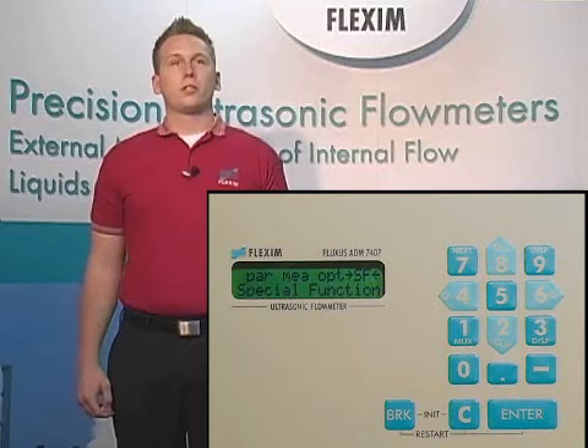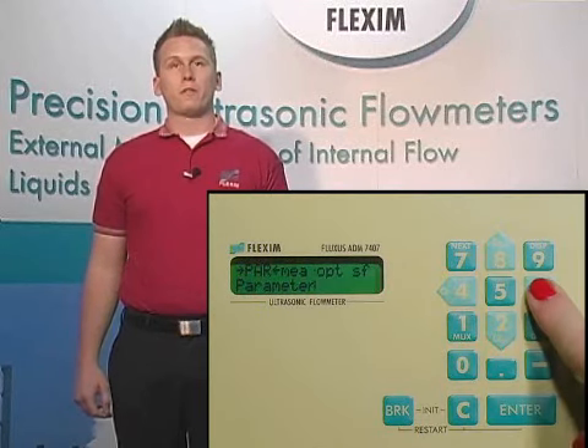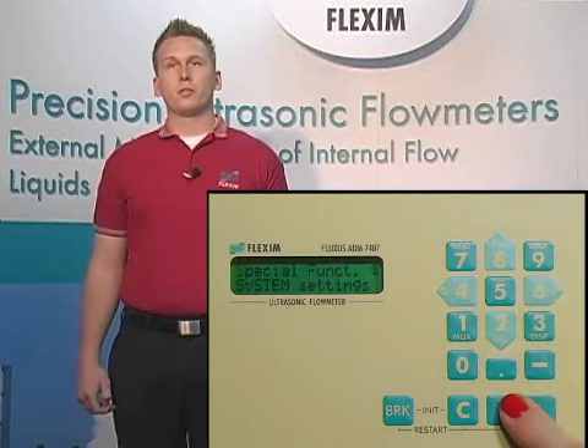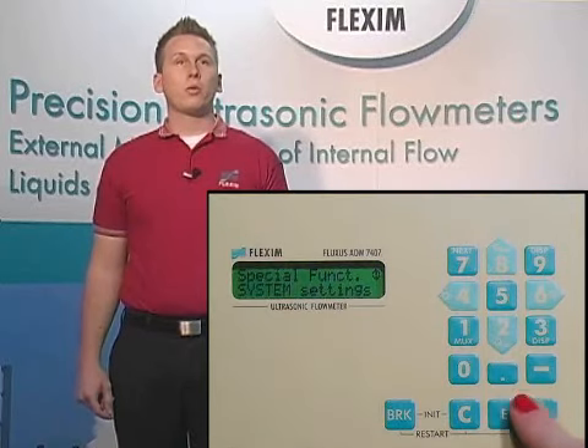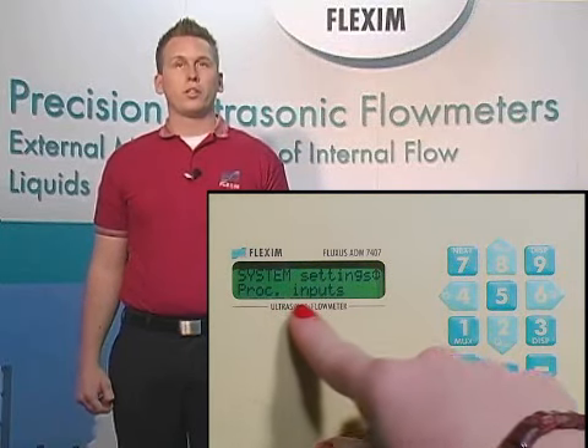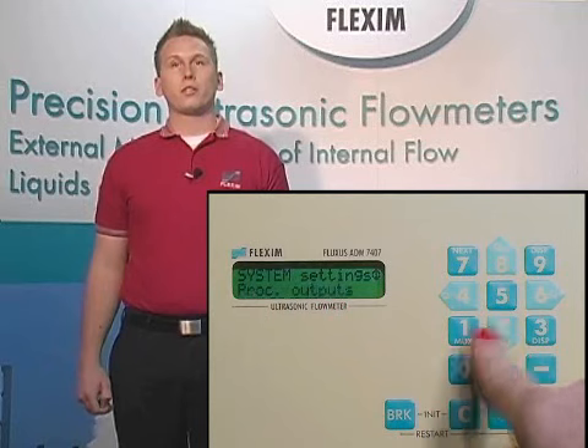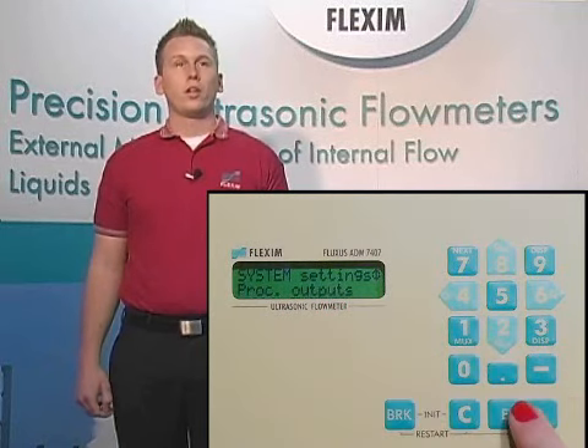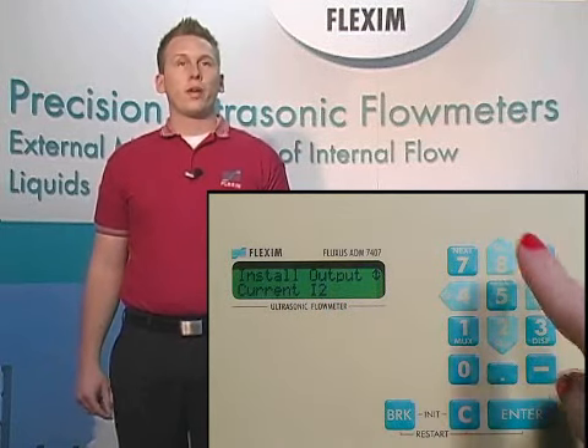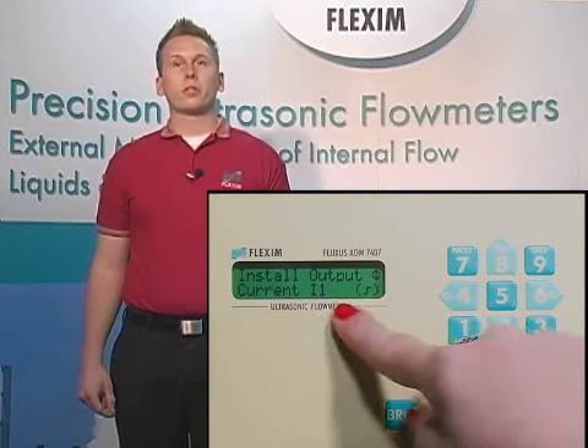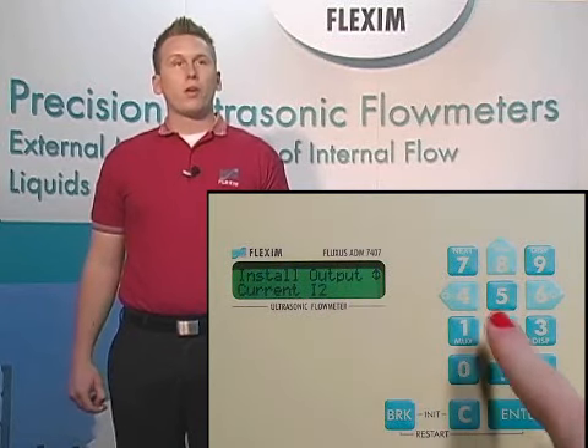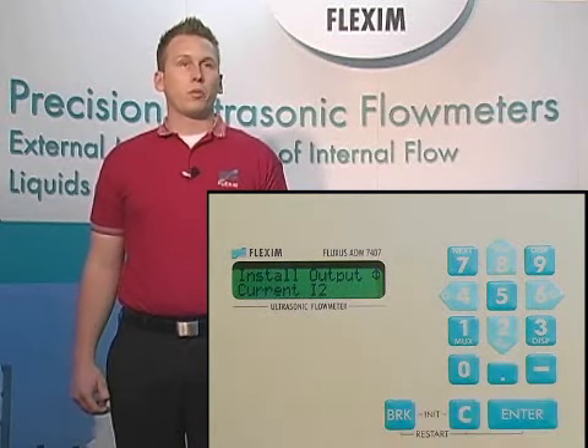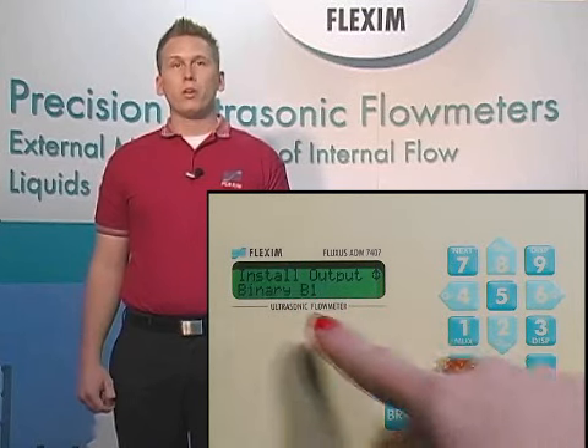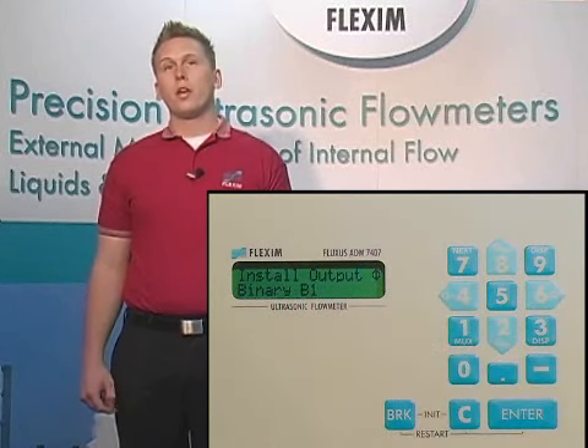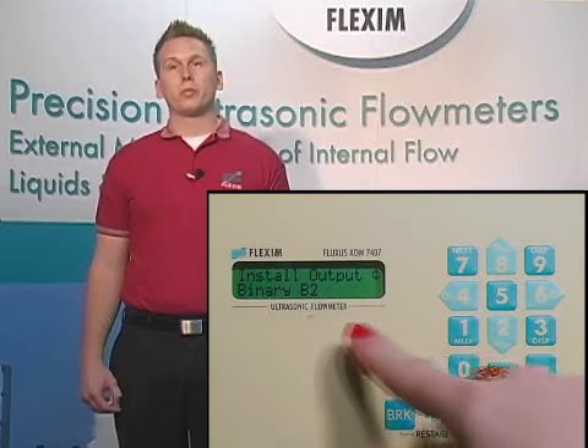The process output section of special functions is found by first going to the special functions menu and hitting enter. Then scrolling down until we see process outputs. Hit enter to go into the process outputs menu. Scrolling up and down here, we have several options depending on how your meter was configured or ordered. We have I1 and I2 for 4 to 20 outputs. We also have B1, B2, and sometimes F1 for binary and frequency outputs respectively.